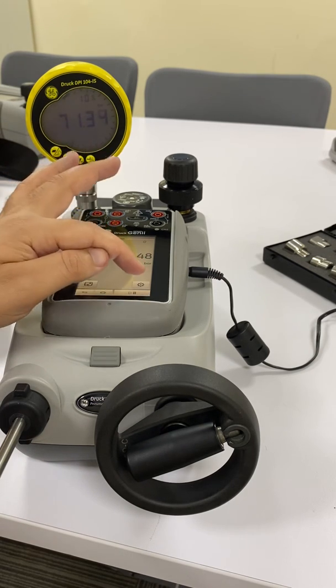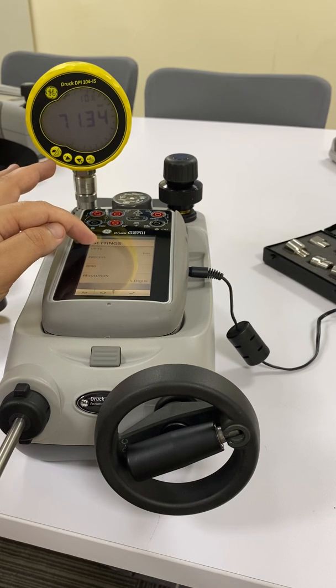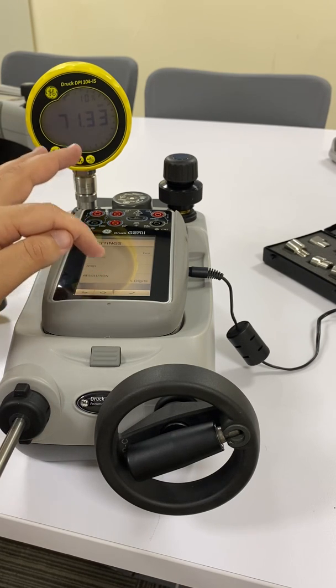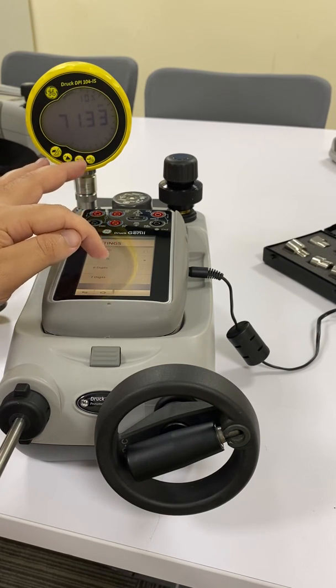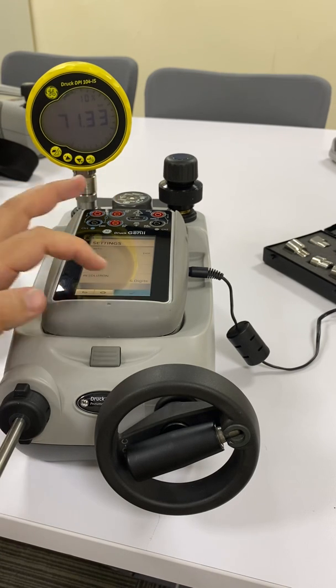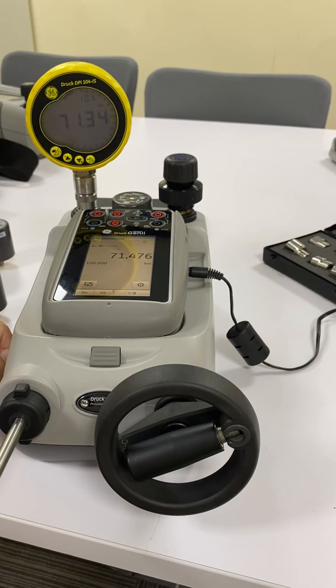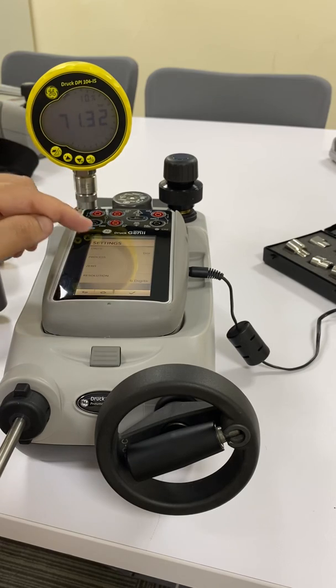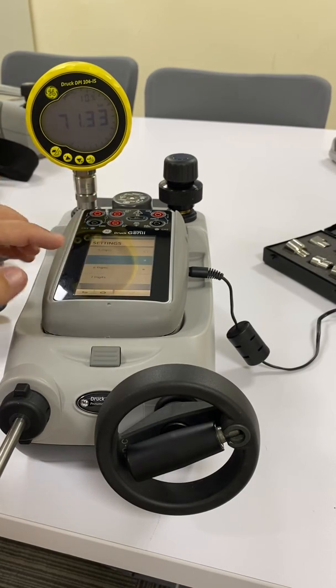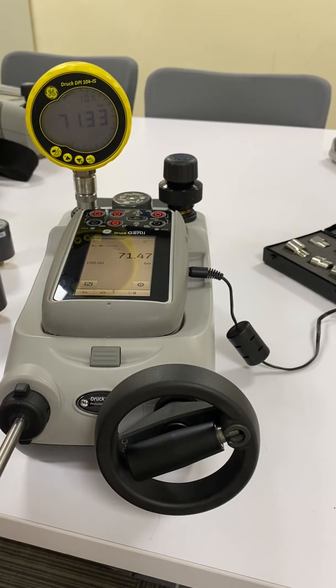If you increase it, let's increase it by 1 digit and see. Okay, resolution. See, it's stable on 3 digits. It will take some time, but it's going up and down, which means that it's not a leak, it's a temperature effect. Let's go back to our resolution to match the device and the test resolution and wait for quite some time.